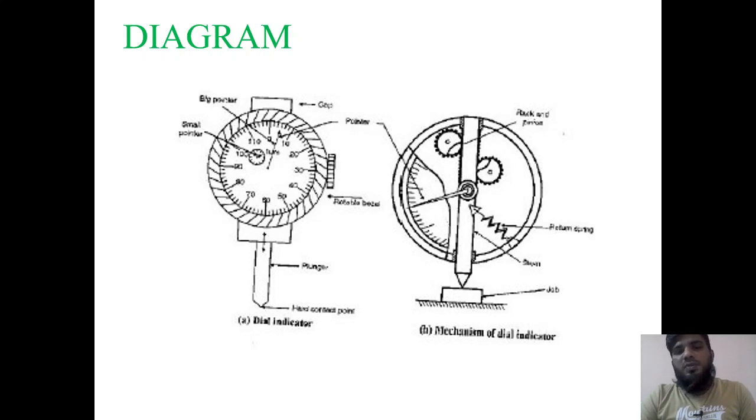So for example, if you are getting a deviation like 0 to 40, it means it is a huge deviation. If you are getting 0 to 10, it is an acceptable deviation. Once you are done with the operation and want to reset, there will be a cap which you can press, and you can reset the deviations.